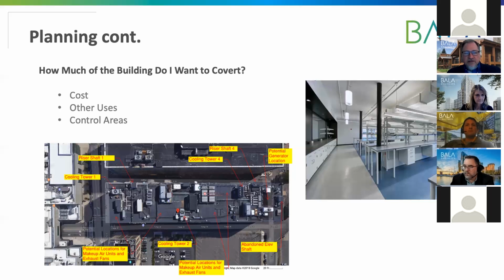We do the cost analysis based on power. What can you physically do? And your first metric is, okay, I have so many watts available, so much kW available. I run out of power at this many square feet of lab. Or I need to add cooling towers, exhausts. I run out of space on the roof to serve this many square feet of lab. So you develop a matrix that has what your breakpoints are. So if I can support more mechanically than I can electrically, I bring in a service and I make them match up. And that's the amount of space that we can convert to a lab. That's part of the analysis and planning that we do up front.